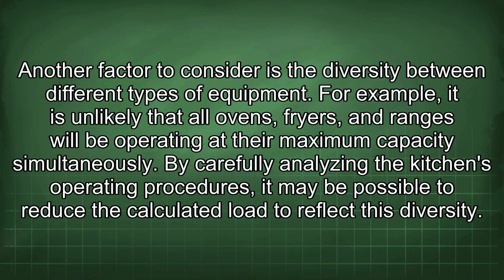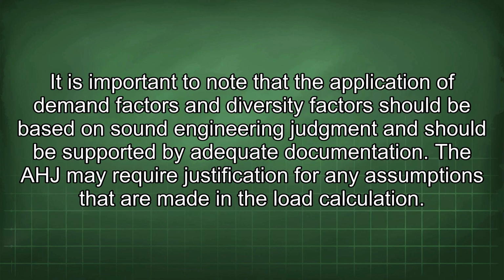Another factor to consider is the diversity between different types of equipment. For example, it is unlikely that all ovens, fryers, and ranges will be operating at their maximum capacity simultaneously. By carefully analyzing the kitchen's operating procedures, it may be possible to reduce the calculated load to reflect this diversity. It is important to note that the application of demand factors and diversity factors should be based on sound engineering judgment and should be supported by adequate documentation. The AHJ may require justification for any assumptions that are made in the load calculation.